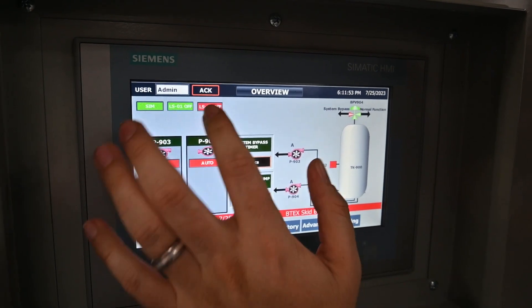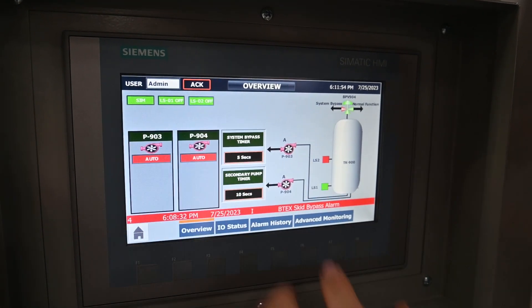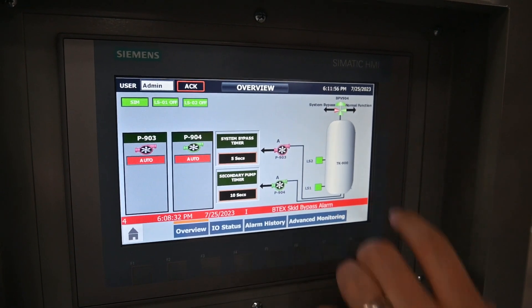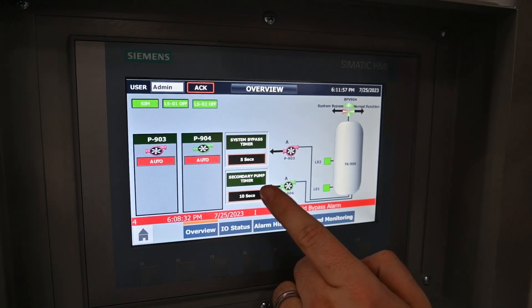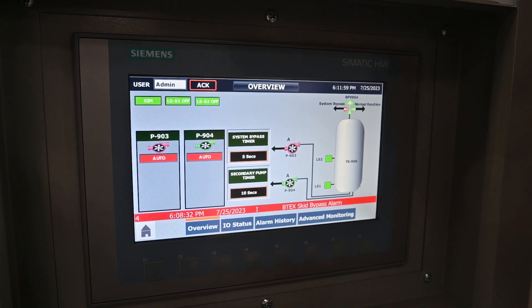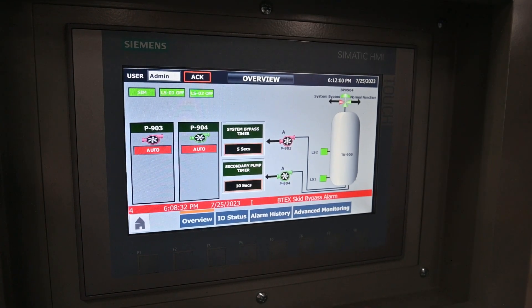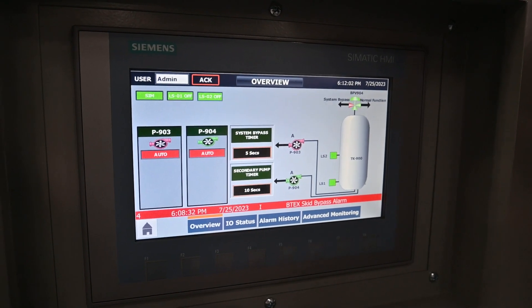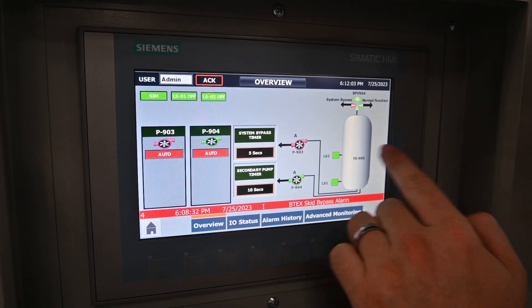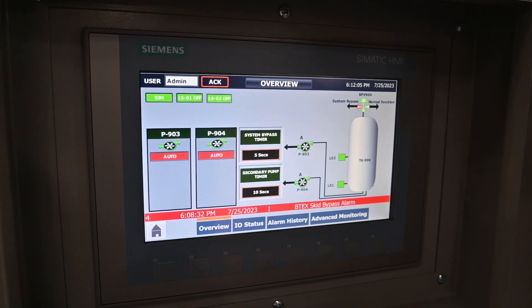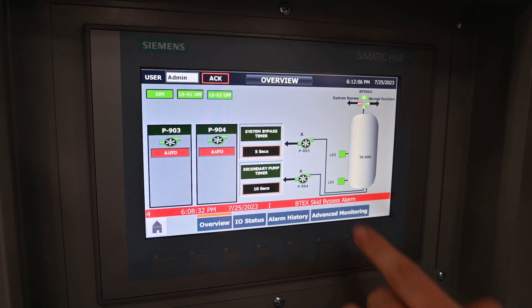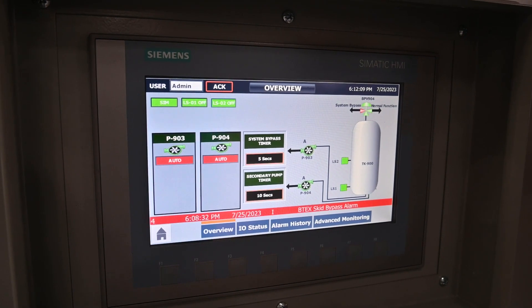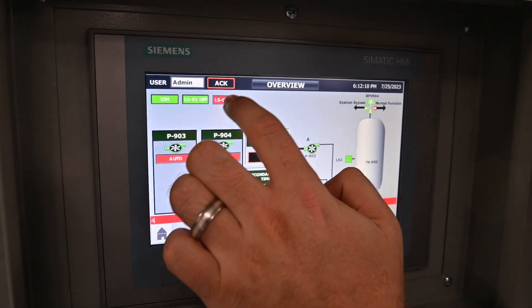If, for whatever reason, your condensate rises to LS2, and right now we have it set to a 10 second timer, if after 10 seconds liquid is not able to be purged back below LS2, it will kick on your secondary pump.